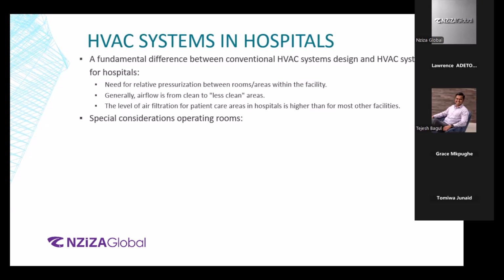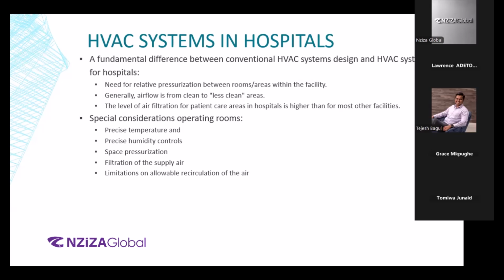The filtration. If you are designing, let's say, an office building, a MERV 8 to MERV 12 filter is more than sufficient. You don't have to hit the HEPA filter mark just because there is no need for it. In the hospitals, we have ill patients, and that is why we try to push for HEPA filters, right? So the special considerations that come into picture when talking about the operating rooms, again, precise temperatures are required, as we checked from the table. Precise humidity controls are required, right? Space pressurization is required. The filtration of supply air is required. And there are limitations to allowable recirculation air. As I mentioned, it needs to be a laminar flow. You cannot recirculate the room with the same air. It needs to go out. Ventilation effectiveness, as I was mentioning, the minimum outdoor air per hour that we require.